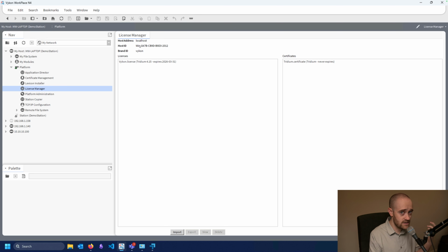The 8000 will not run without the SD card in and being recognized by the JACE. And then in the 9000, there's kind of a weird thing that happens where if the SD card isn't in, you'll get one host ID, and if you put the SD card in, you'll get a different host ID. And that's the host ID you actually want to use, the one with the SD card. The host ID will have an SD in the string of characters here.